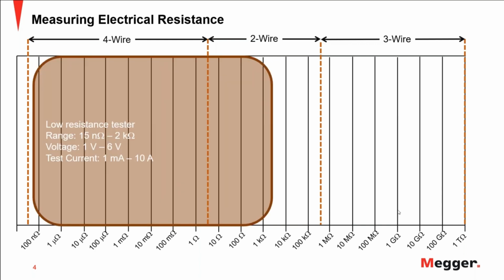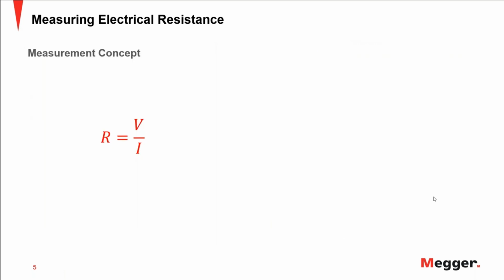And then you have what are called the low resistance testers, or digital low resistance ohmmeters. And they can go from anywhere from 15 nano ohms to 2 kilo ohms, with voltages from 1 to 6 volts and test currents from 1 milliamp to 10 amps. So this is already telling you that resistance measurement is something that I definitely need to understand, and I need to know what tool I'm going to be using for the application that I have.